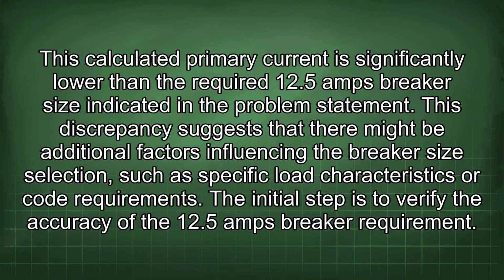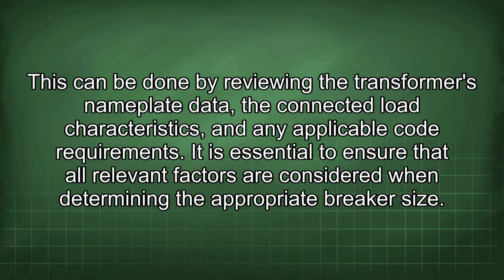characteristics or code requirements. The initial step is to verify the accuracy of the 12.5 amps breaker requirement. This can be done by reviewing the transformer's nameplate data, the connected load characteristics, and any applicable code requirements. It is essential to ensure that all relevant factors are considered when determining the appropriate breaker size.